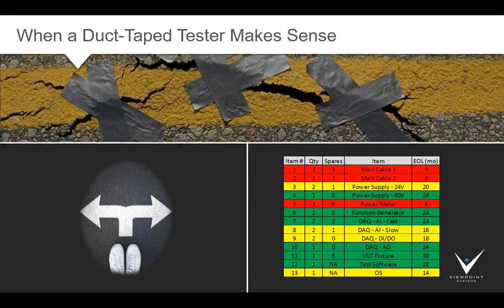One thing I'll mention is to pay attention to interactions between the tester components. For example, upgrading an old obsolete analog card might be great until you upgrade the operating system, because as soon as you do that, you have to upgrade the PC since the drivers aren't available anymore. So there might be a cascade that you have to watch for.